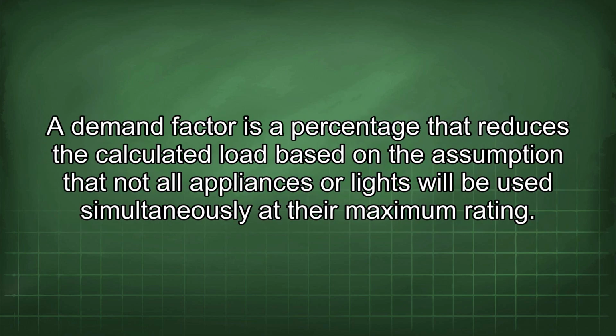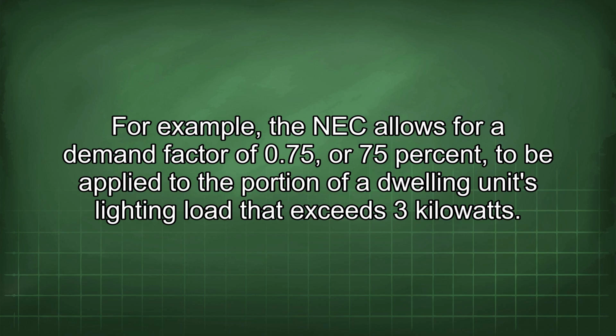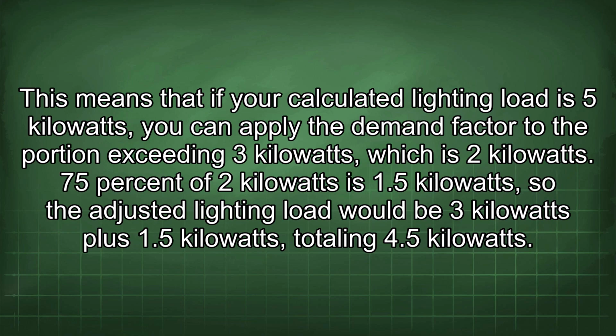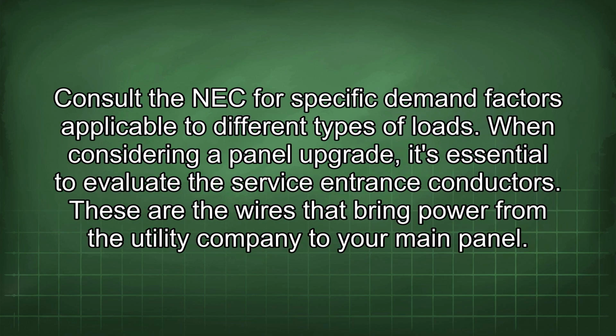A demand factor is a percentage that reduces the calculated load based on the assumption that not all appliances or lights will be used simultaneously at their maximum rating. For example, the NEC allows for a demand factor of 0.75 or 75% to be applied to the portion of a dwelling unit's lighting load that exceeds 3 kilowatts. This means that if your calculated lighting load is 5 kilowatts, you can apply the demand factor to the portion exceeding 3 kilowatts, which is 2 kilowatts. 75% of 2 kilowatts is 1.5 kilowatts, so the adjusted lighting load would be 3 kilowatts plus 1.5 kilowatts, totaling 4.5 kilowatts. Consult the NEC for specific demand factors applicable to different types of loads.